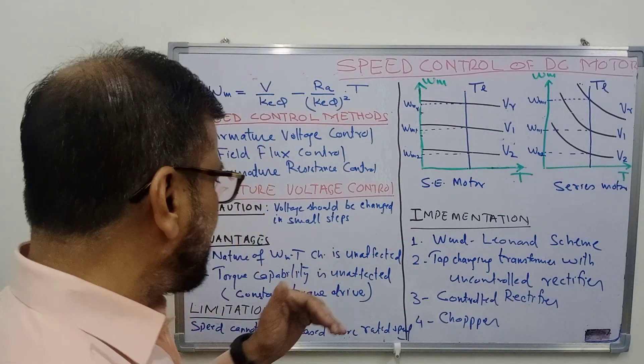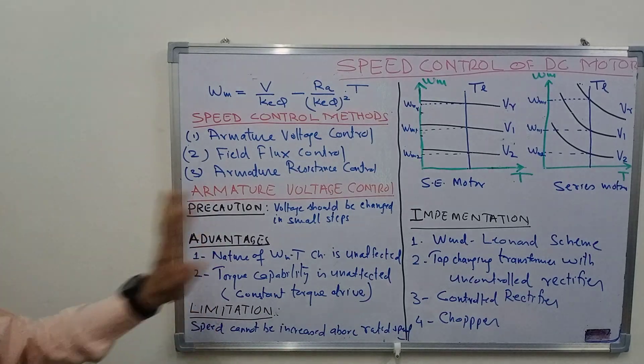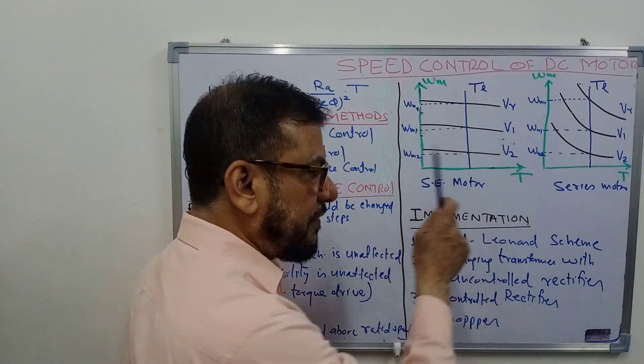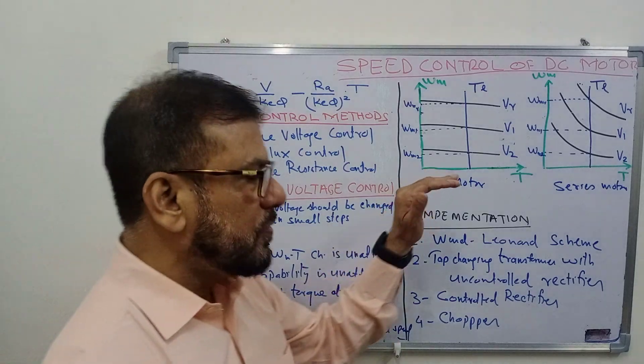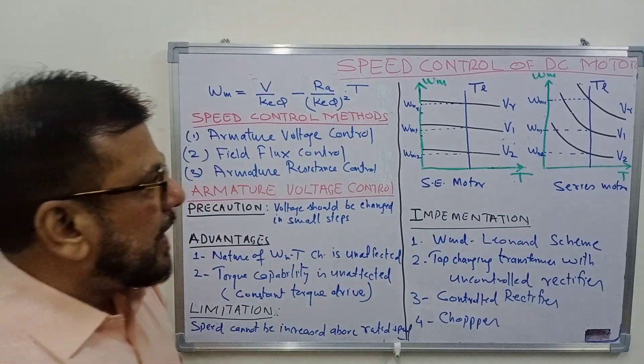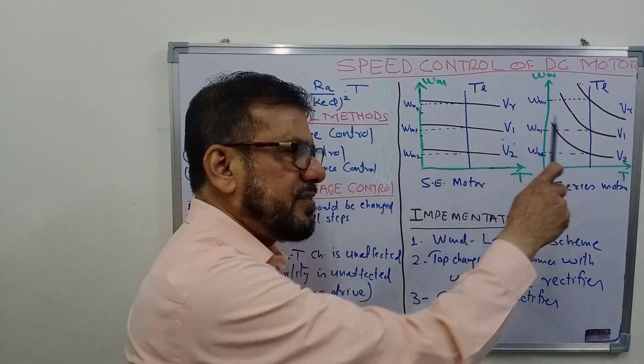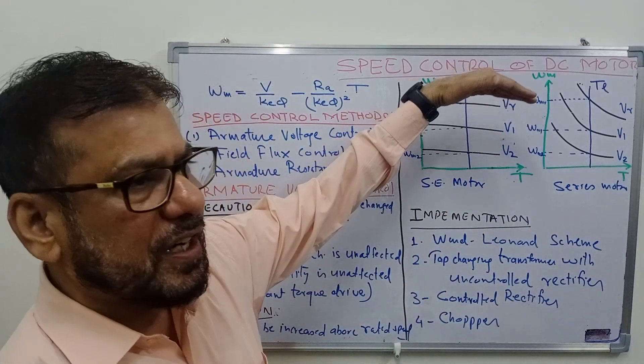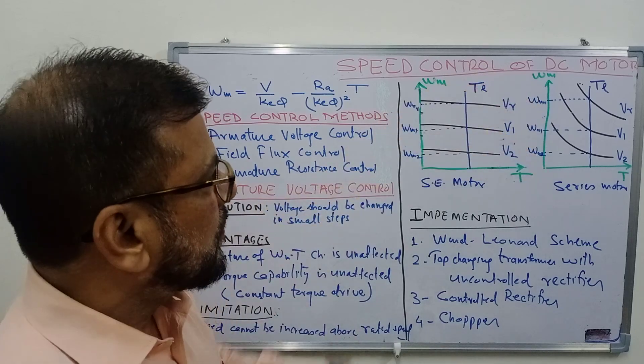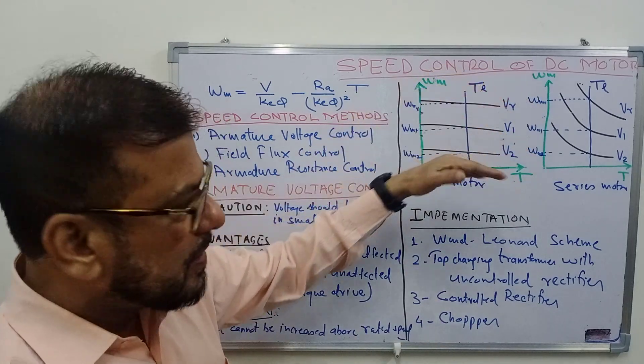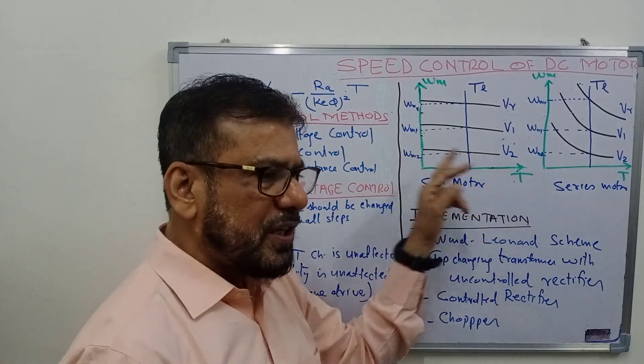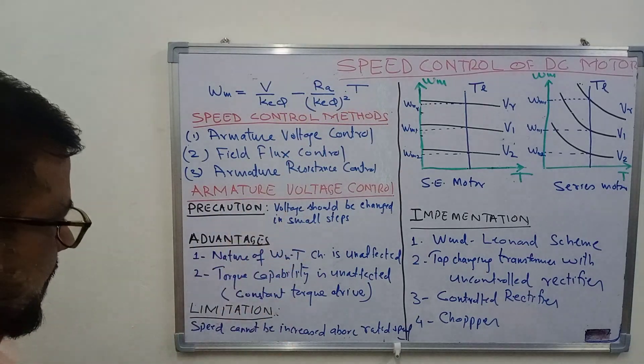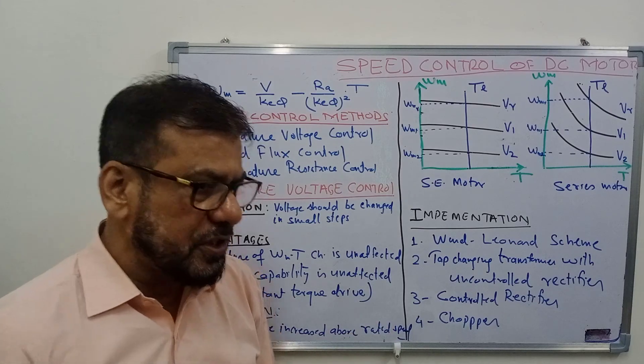The advantages of this method are as follows. First, the nature of the speed-torque characteristic is not affected. For example, if you are using a separately excited DC motor requiring good speed regulation, that characteristic is maintained. The change in speed from no load to full load remains the same as at rated voltage. So speed regulation is preserved — this is one advantage of armature voltage control.